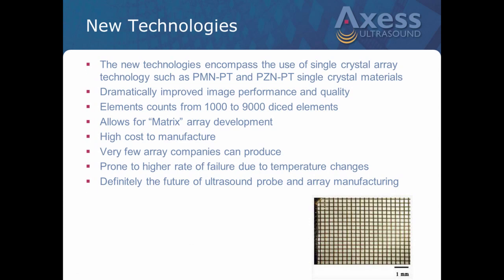So some of the new technologies that have really come to the forefront, and probably the most popular one, is what we call single crystal array. I'll explain what these are, but it's just PMN-PT and PZN-PT single crystal materials. If you remember from previous slides, the PZT arrays are typically individual elements, up to 64 to 288 elements, and each one of those elements is connected via wire through the probe head, in through the probe cable to the system end connector. And it's got a send-receive signal on each element.